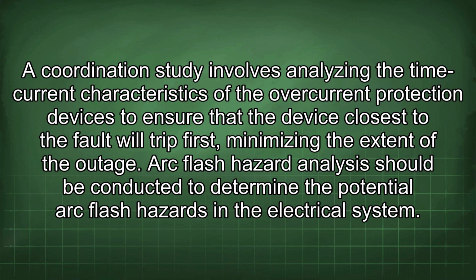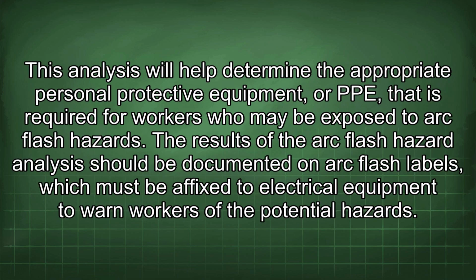Arc flash hazard analysis should be conducted to determine the potential arc flash hazards in the electrical system. This analysis will help determine the appropriate personal protective equipment, or PPE, that is required for workers who may be exposed to arc flash hazards. The results of the arc flash hazard analysis should be documented on arc flash labels, which must be affixed to electrical equipment to warn workers of the potential hazards.